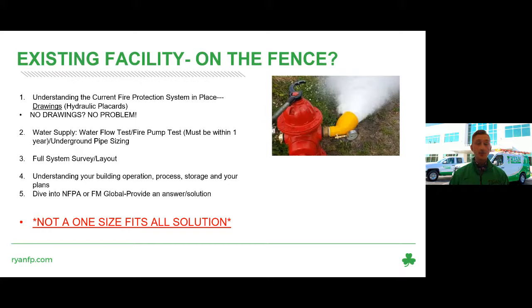Next is water supply, which is very, very important. We'd want an updated water flow test or fire pump test, and that has to be within the last 12 months. If you handed me a test that's 13 or 14 months old, I'd probably want to do another flow test just to verify the information is correct. For those without fire pumps, we'd be flowing hydrants - you can see a picture here of us grabbing a gallons-per-minute reading with a pitot gauge.